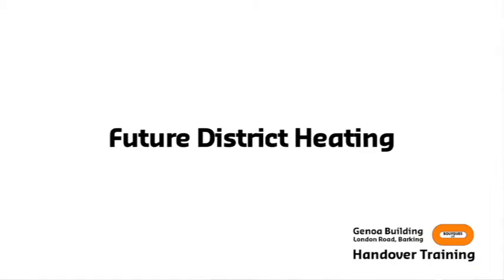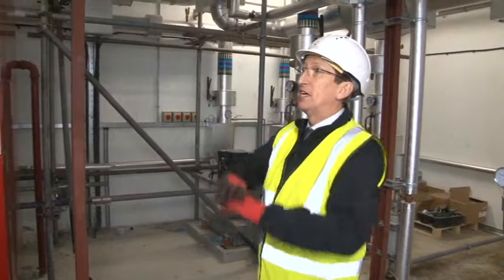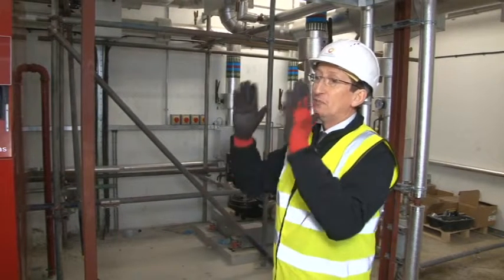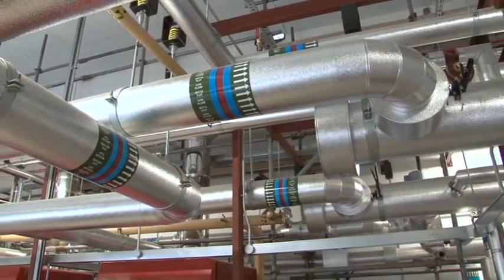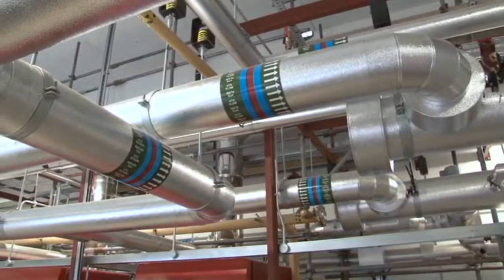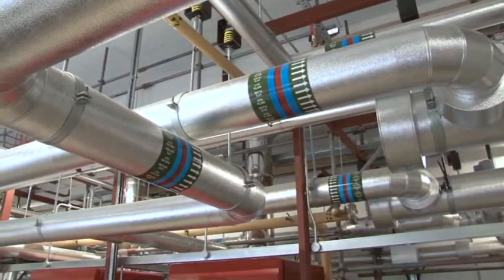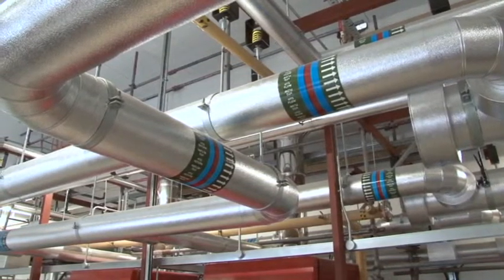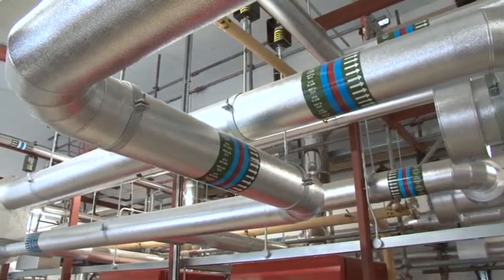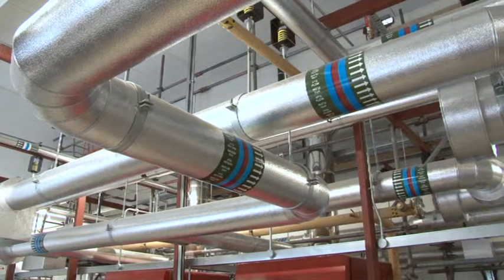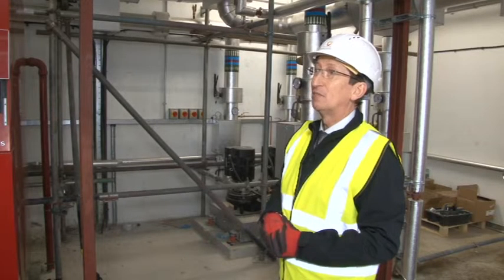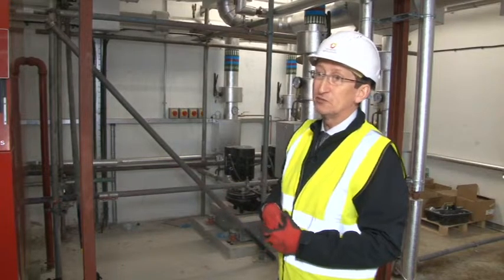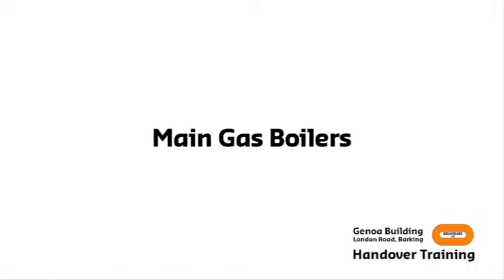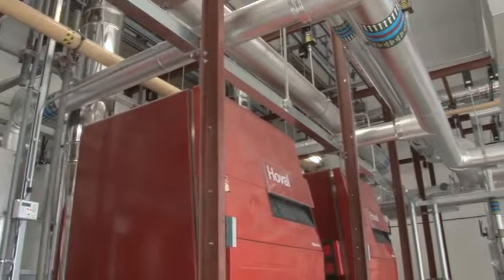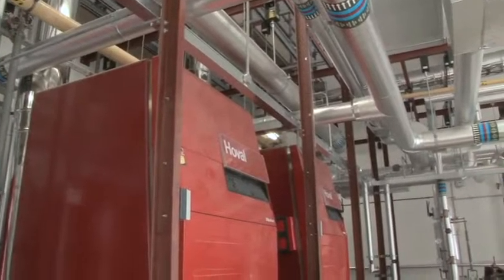What we've also got above your heads literally are two pipes there with dead ends on them, and they're for a provision for connecting into a future district heating system, which should be a Barking wide area district heating as I understand it. So that would in effect take over from the boilers and the CHP in here if and when that comes to fruition. But that provision is already built into the system to take over from that. The main heat providers then are the two red boilers behind you. So we've got two 1,000 kilowatt boilers there.